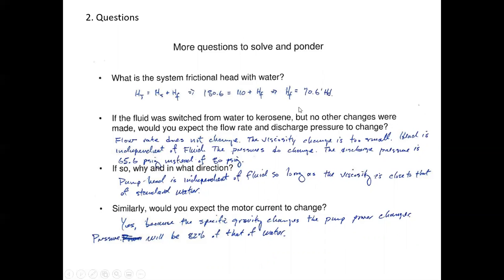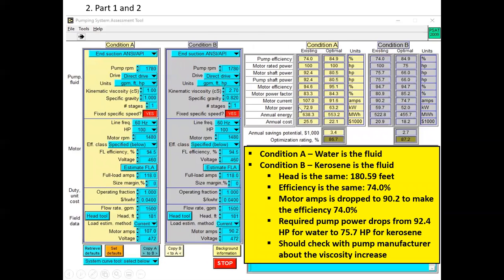Viscosity change is too small. Head is independent of the fluid. The pressures do change. Discharge pressure is 65.6 PSIG instead of 80. If so, why and in what direction? Well, I think we've already answered that. And similarly, would you expect motor current to change? And yes, because the specific gravity says this kerosene is lighter, so it's roughly 82% of that of water, and we already talked about the actual numbers right here.